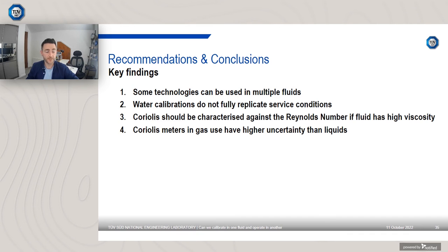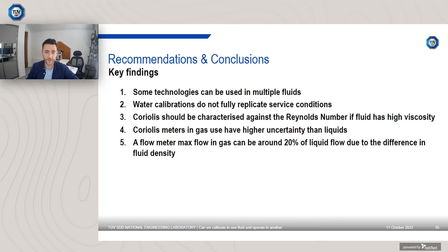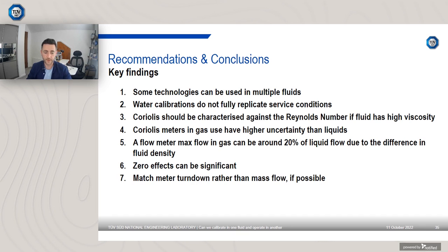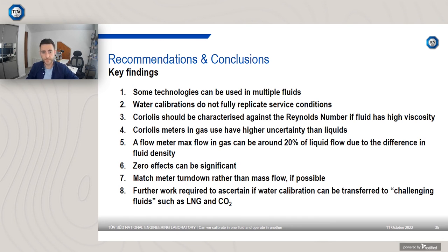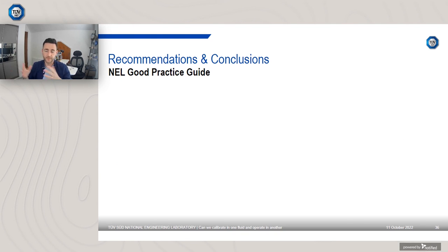Coriolis meters in gas have a higher uncertainty than in liquid. Again, not everyone's fully aware of that. They don't expect the same performance. And crucially, you'd have to account for that further uncertainty contribution of a different fluid medium. And at present, I would say there's not enough empirical data to give you a good feeling for the effect of, say, LNG compared to water. A flow meter's max flow in gas can be around 20% of liquid flow rate due to the difference in fluid density. Zero effects can be significant, so please account for that. And you should match the meter turndown rather than mass flow if possible. And as I said, there's further work required with respect to the performance in alternative fluids such as LNG and CO2.